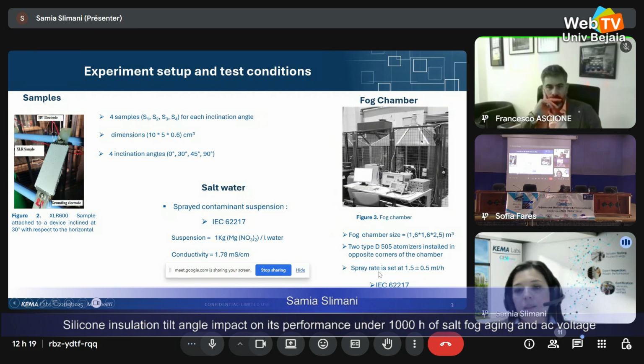The spray rate was set at 1.5 plus minus 0.5 milliliter per hour, according to the standard IEC 62217. The salt water was also prepared following the same norm. It's obtained by adding 1 kilogram of magnesium nitrate to 1 liter of water.